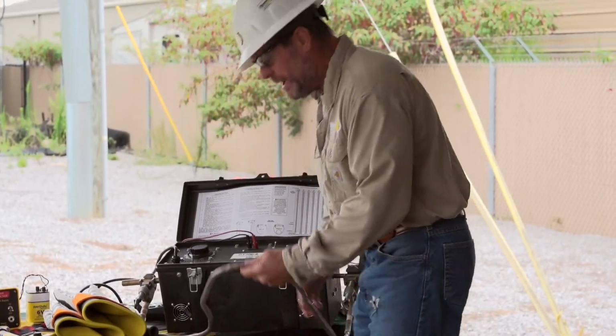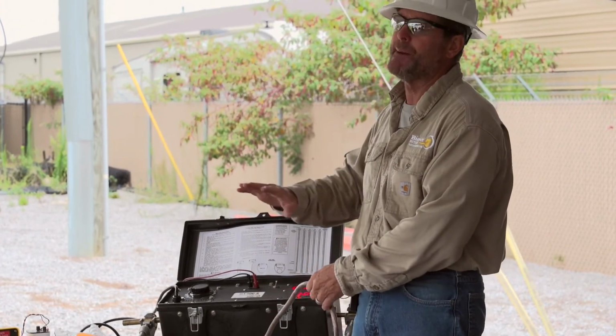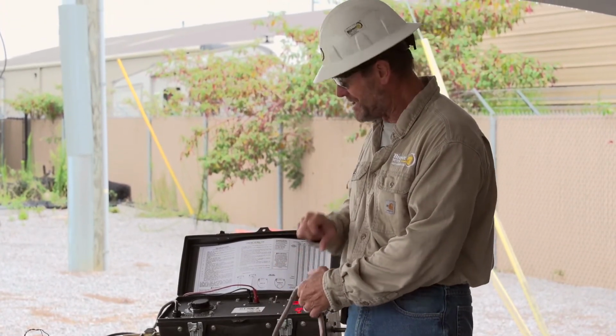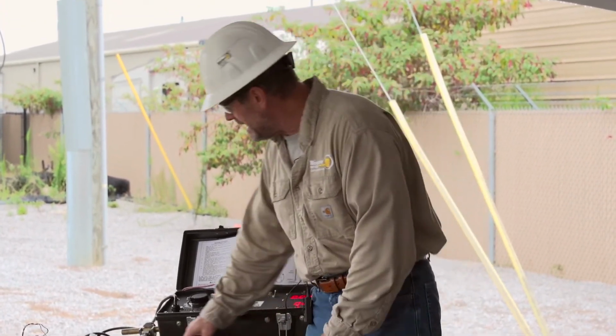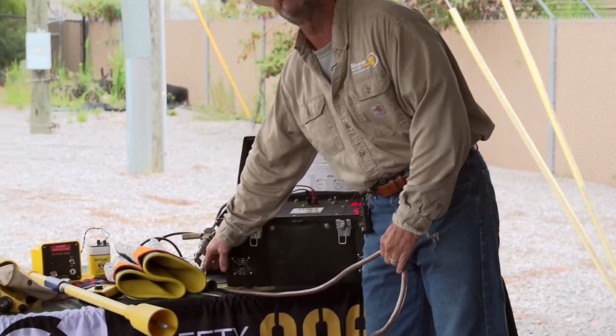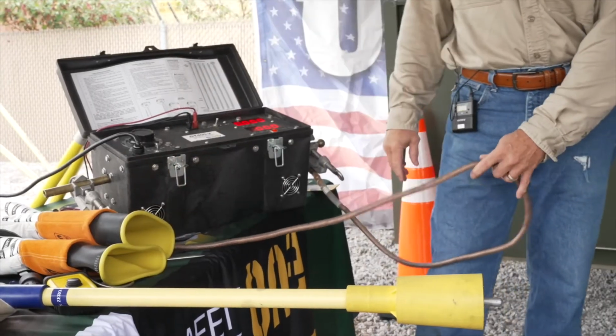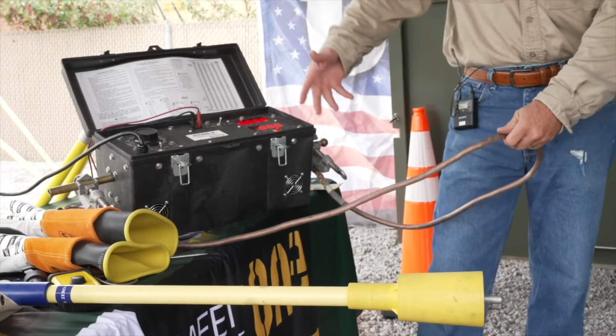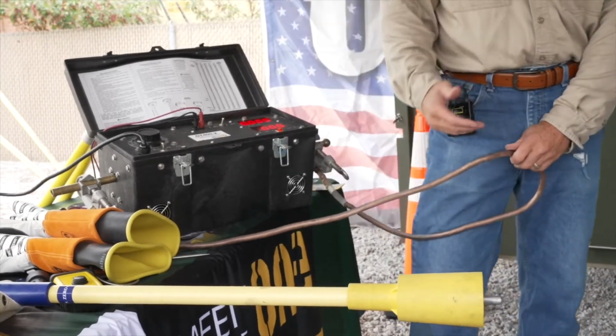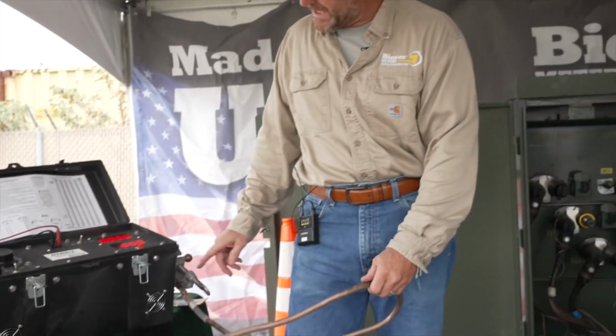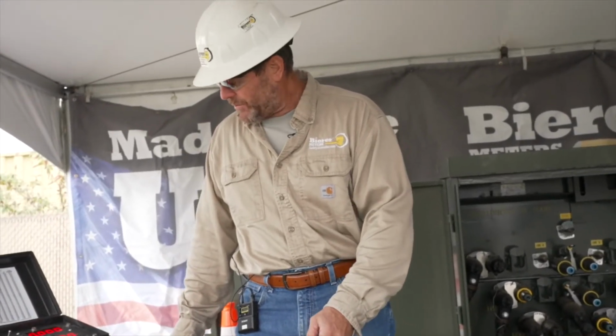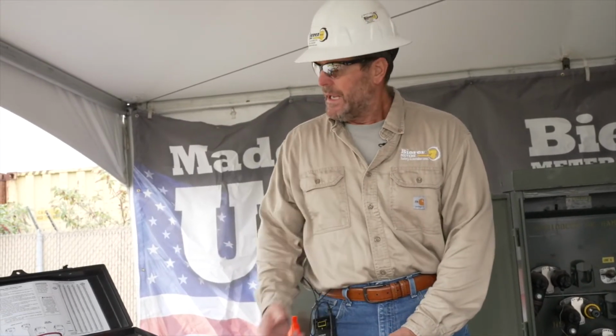Visual inspection: you're going to look for an absence of any pinched or smashed cable. You do not want to see any blackened or patinaed copper. You don't want to see any broken strands—if you can see through your jacket, you don't want to see any broken strands. You don't want to see any cracks on your clamps, and no obvious loose connections that even look loose. Make sure everything looks good.